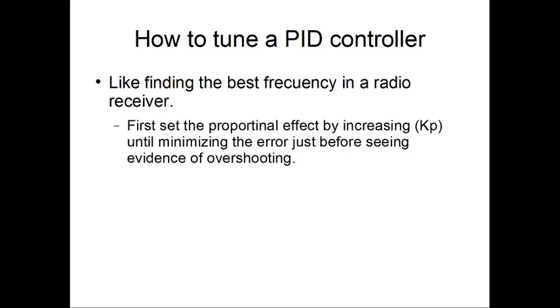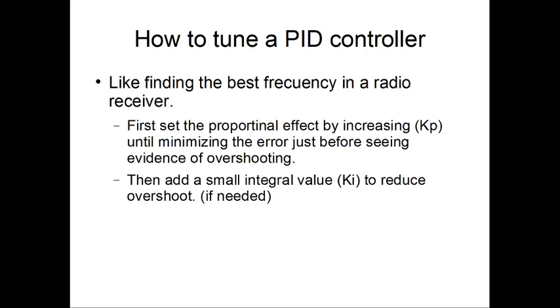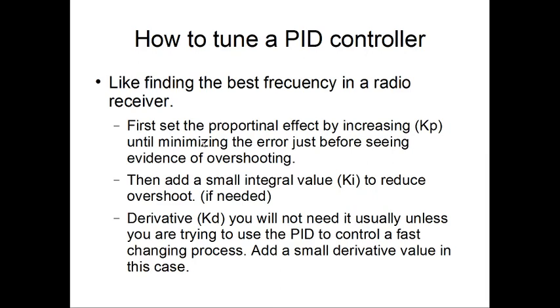First, set the proportional effect by increasing Kp until minimizing the error just before seeing evidence of overshooting. Then, add a small integral value to reduce overshoot. The derivative effect, you will not usually need it unless you are trying to use the PID to control a fast-changing process. If this is the case, add a small derivative value for this particular case.